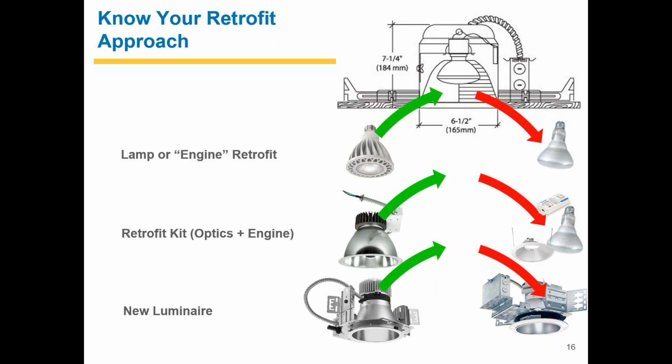One of the great examples here is we did a lighting audit of a warehouse that they turned into an office space for a startup, and they had 400-watt metal halide acrylic high bays, and they were like, we're not really comfortable doing office tasks in here. Our eyes hurt. It's just not working for us. And it's kind of like, well, you moved into a warehouse, you probably should have retrofit the lighting at the same time. And so these are the cases where the new luminaire retrofit might be a good call.